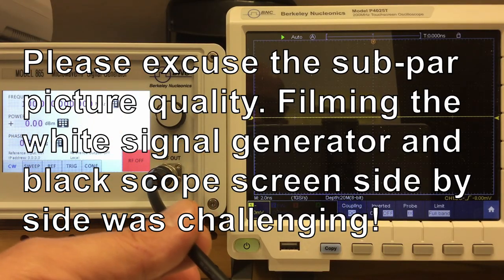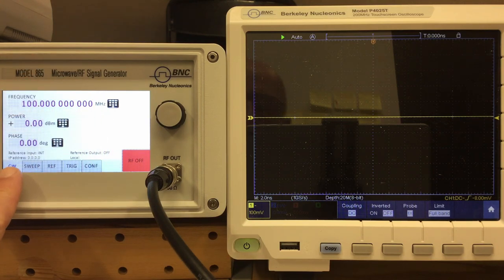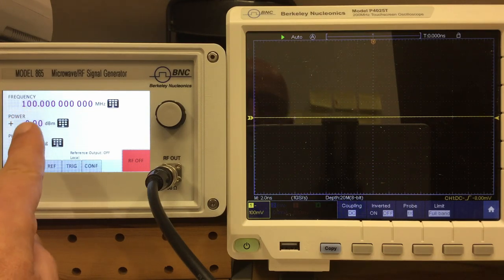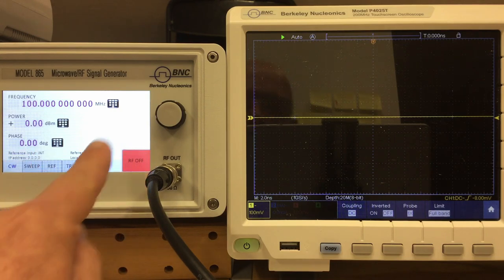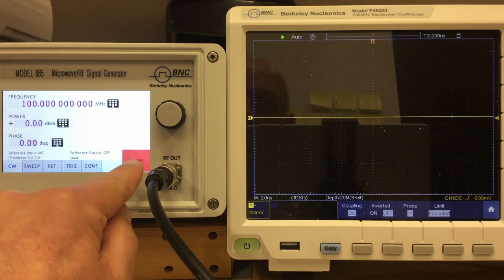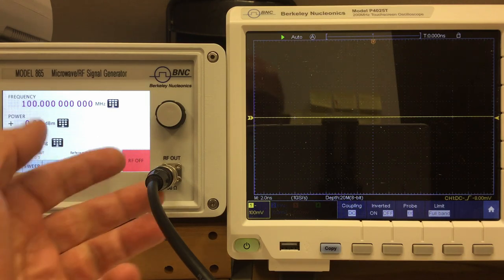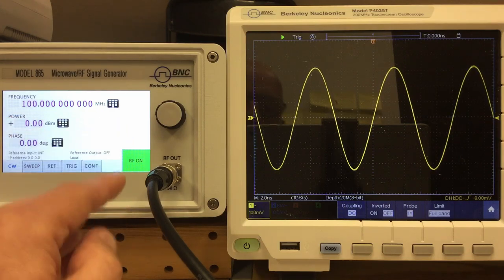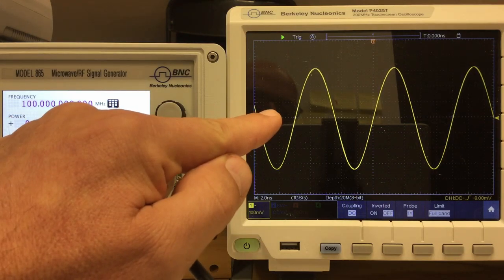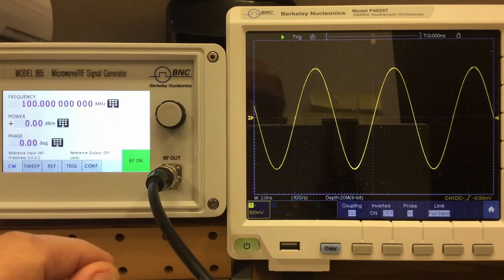I connected the oscilloscope with a little adapter and a BNC cable with a 50-ohm terminator at the end. After you power up the unit, you will find yourself in the continuous wave menu or CW menu. You have basically three parameters here: frequency, power, and phase, and that big red RF off button. When we touch it, it will switch on the RF output and get green RF on, and we have the output signal from the unit on the scope.